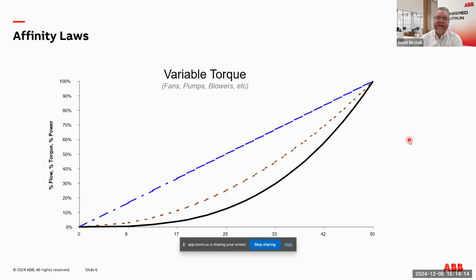So I mentioned energy savings, so that's where the affinity laws come in. There's three main ones there. Your airflow is directly proportional to speed. So I look at this graph right down here. This is 0 to 50 hertz. This is my speed on the bottom. And then here's my percent, either flow, torque, or power, depending which variable we're talking about.